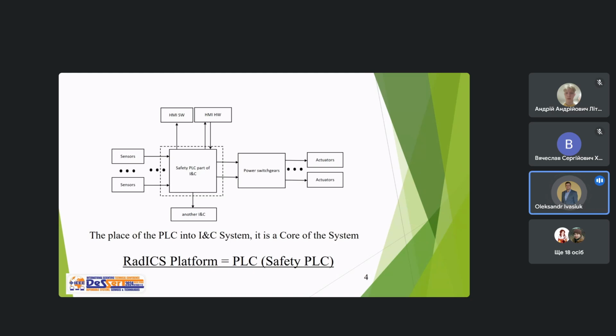On this slide, you can see the general schema of the I&C system. If the I&C shall perform the safety function, for example to stop some technological process at the plant, this I&C will be considered as the safety I&C. The core of such type of system is the Programmable Logic Controller, PLC, which gathers signals from different sources, processes them, and generates control commands to actuators and different annunciation signals. The main object of the presentation is a safety PLC called the RadICS Platform.